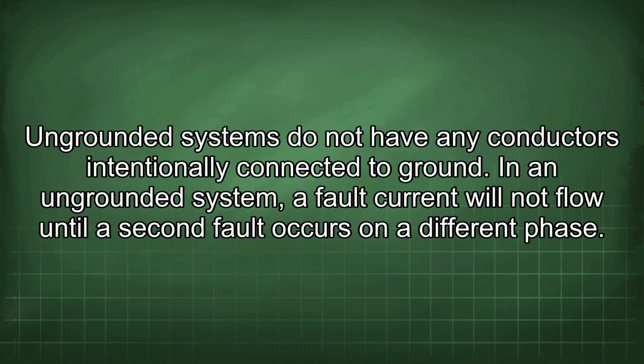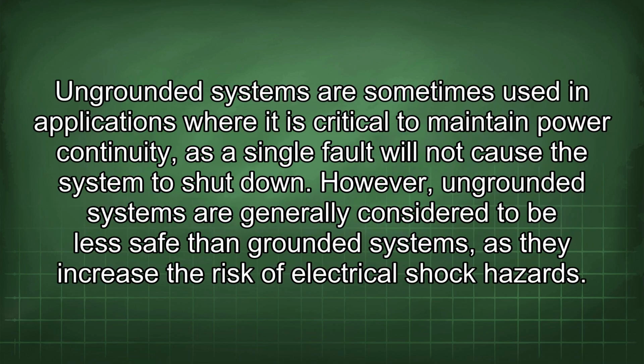Ungrounded systems do not have any conductors intentionally connected to ground. In an ungrounded system, a fault current will not flow until a second fault occurs on a different phase. Ungrounded systems are sometimes used in applications where it is critical to maintain power continuity, as a single fault will not cause the system to shut down. However, ungrounded systems are generally considered to be less safe than grounded systems, as they increase the risk of electrical shock hazards.